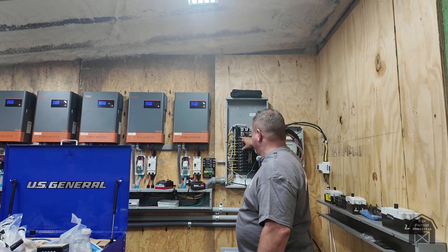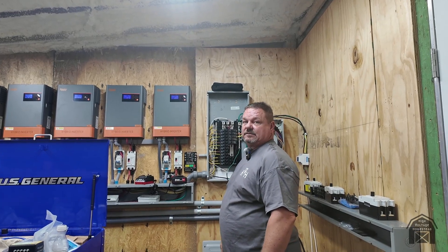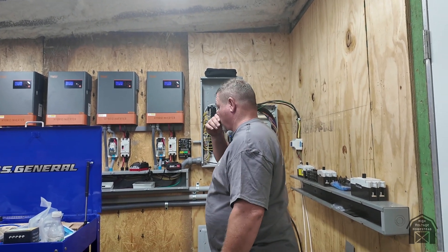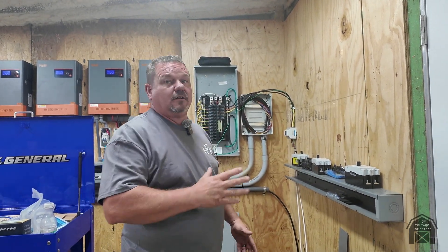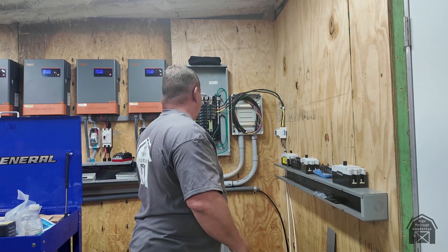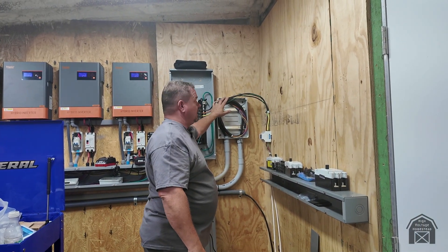Each inverter puts out roughly 30 amps, so 30 amps times four gives you 120 amps total on each phase. Currently we're pulling about 35 amps because we only have four inverter units running off this setup right now. This is obviously just temporary.